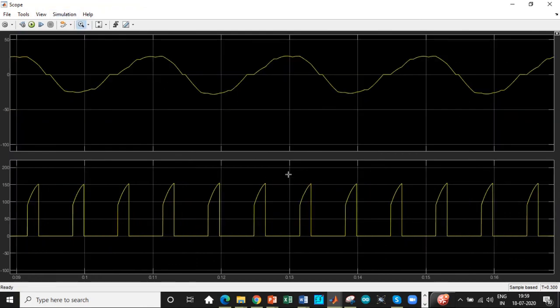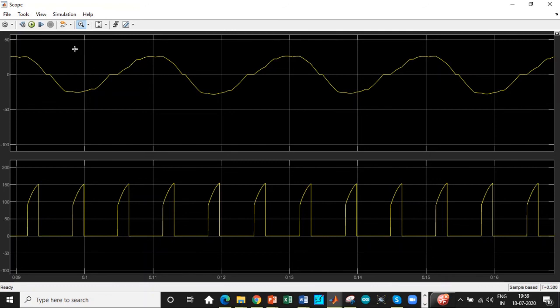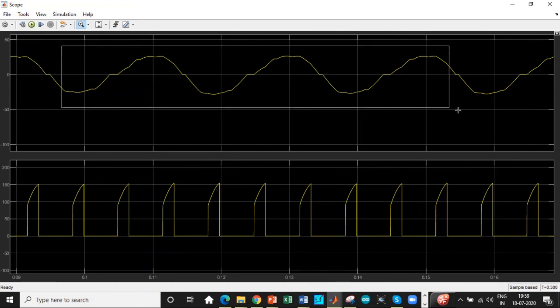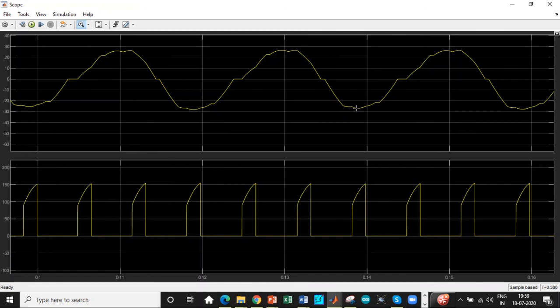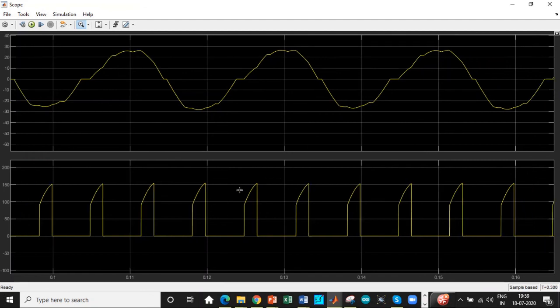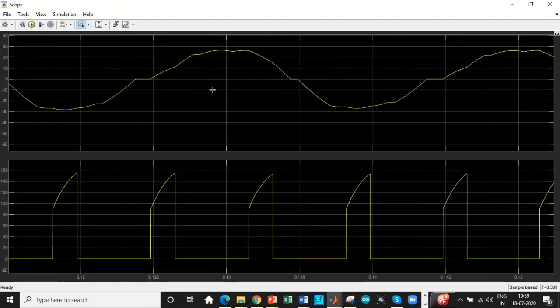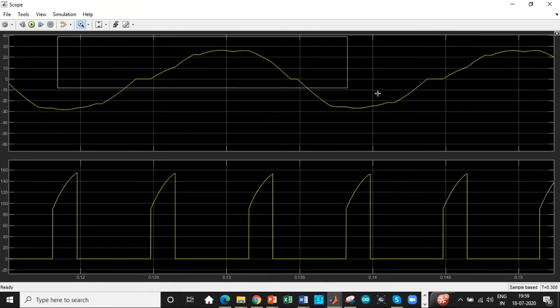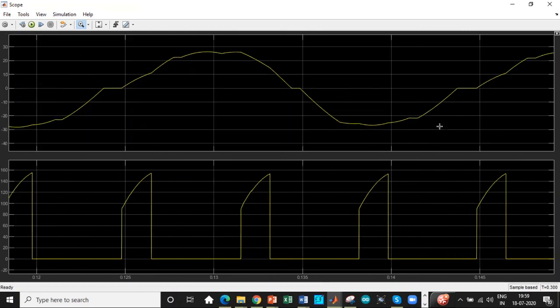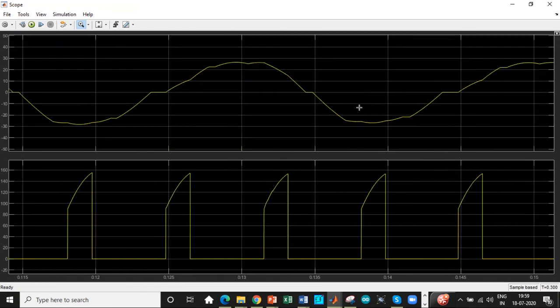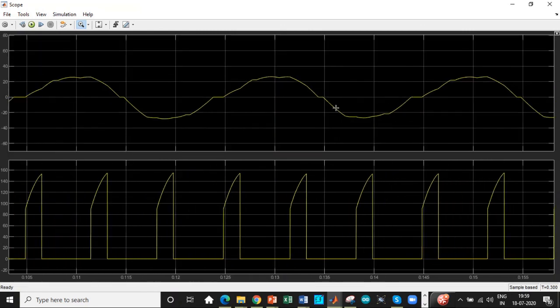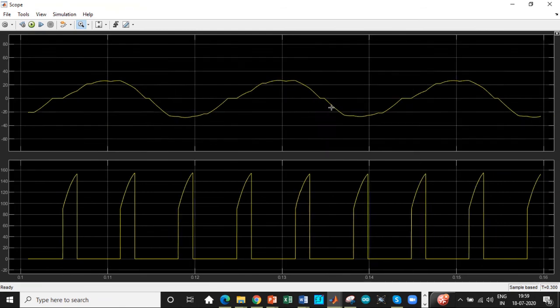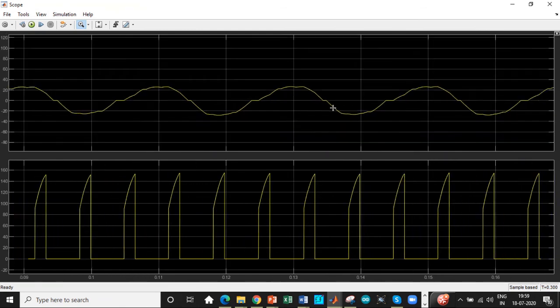Here you can see there are certain ripples. This is the primary current waveform and this is the output voltage waveform. You can see a lot of ripples with respect to the source current—these are called harmonics and you can suitably reduce them by designing a filter according to power quality techniques. This is the output voltage waveform you're getting. This clearly indicates the harmonics generated are much higher because of the controlled thyristors that are used.